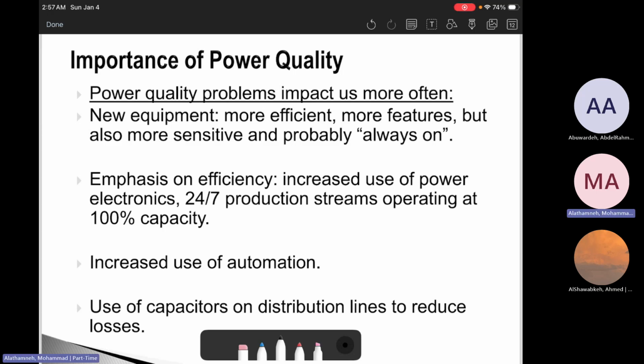Okay, some examples that we can mention in Jordan: large irrigation pumps switching on and off in agricultural areas. We notice this a lot. You can go to the suburbs and you will see large irrigation systems. Those are pumps based on motors, and they switch on and off. These very big motors have high startup currents. That high inrush current makes the current transients very high, which causes a significant voltage drop, and this can impact the customers.